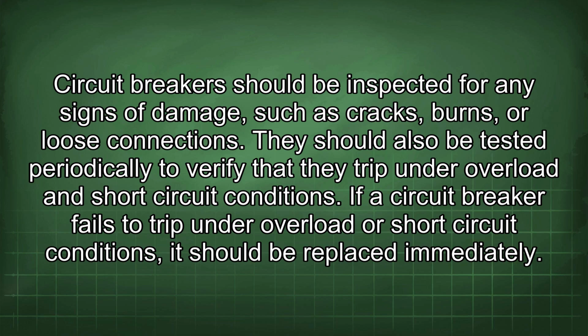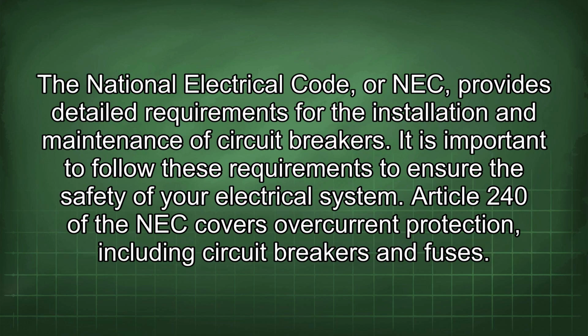If a circuit breaker fails to trip under overload or short circuit conditions, it should be replaced immediately. The National Electrical Code, or NEC, provides detailed requirements for the installation and maintenance of circuit breakers. It is important to follow these requirements to ensure the safety of your electrical system. Article 240 of the NEC covers overcurrent protection, including circuit breakers and fuses.